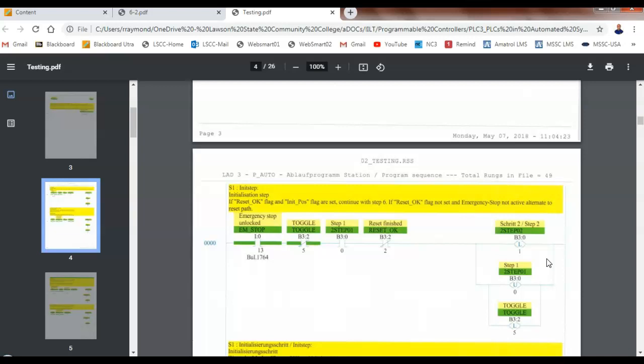In understanding the logic, all I'm trying to do is say, this is what we do with B3 files. B3 files don't need to generate output. All they're doing is they're in the program to make what? And like I said, in motor control, you're going to learn they're called control relays. So a control relay does not have any contact in the power line. They don't turn them on. They don't reverse them over. They just make decisions on when it's going to happen, right?